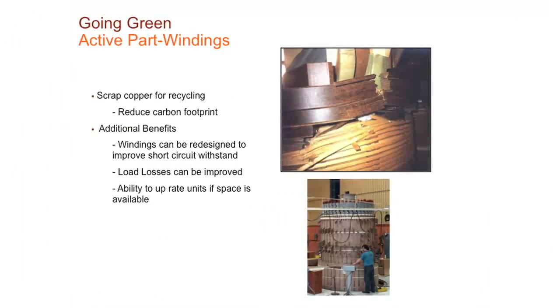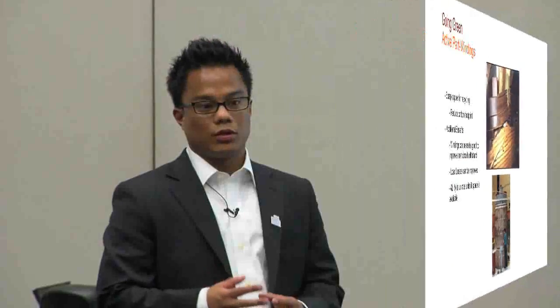The active part and the windings. This is really the beef of the transformer, where the majority of the cost of the transformer is. And if there is a failure in a transformer, this is the area where we see the majority of the failures. When you look at the statistics from Doble, 43% of the failures are in the active part or in the windings. The nice thing about the copper is if there is a failure and it cannot be reused, we typically scrap the copper and sell it back to the metals company, and they can reuse that copper, and then we'll purchase it.